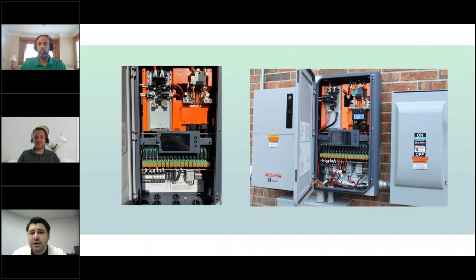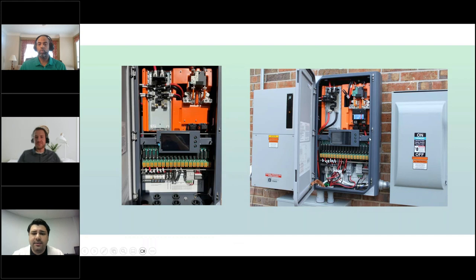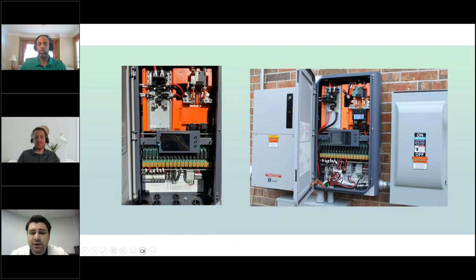Now let's address the cables. On the breaker with the blue sticker — standard breaker for 200-amp service — there are two cables; those are the grid input cables. On the bus bar where the inverter load breaker sits, you see two other cables that go to your main electrical panel. In the bottom we see smaller cables going to the orange-green load shedding elements — the dedicated ones for your generator, EV charger, and AC coupled solar, along with the ones that the customer controls.